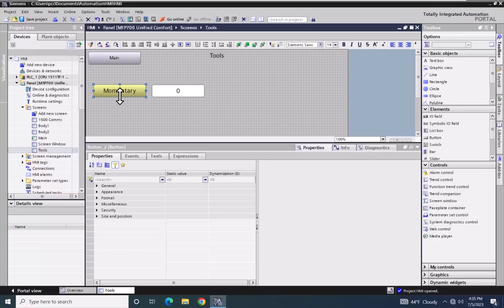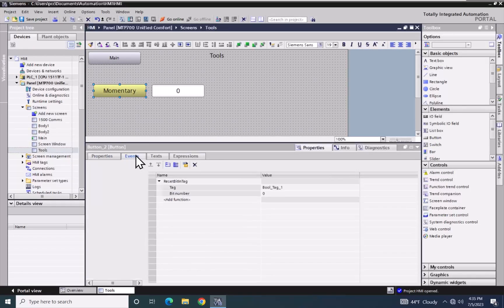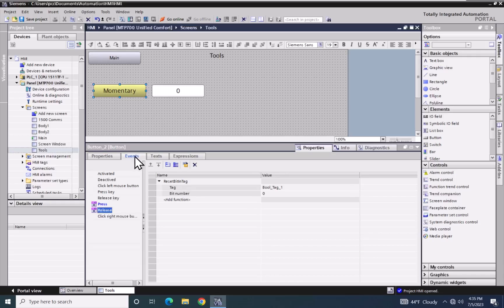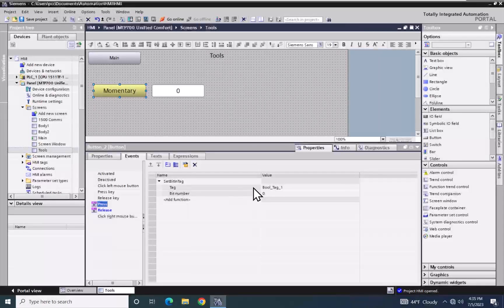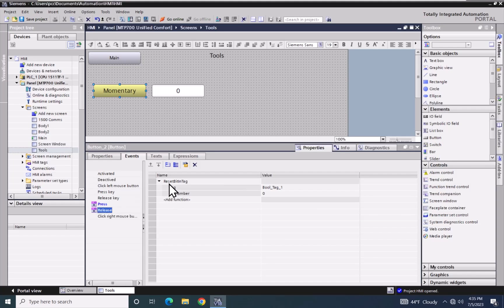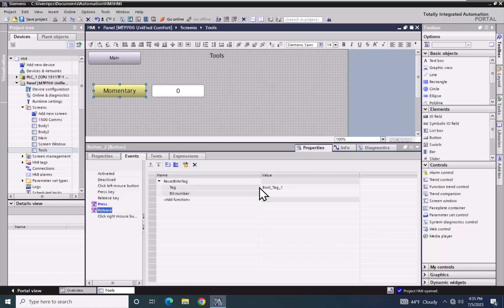I'm going to select the momentary push button and go to the events tab. In the previous lesson we configured the press event to use the set bit in tag, and it's going to write a value of one to the bool tag underscore one when we press the momentary push button. When we select the release event, it is going to execute the reset bit in tag and then reset the bool tag underscore one to a value of zero.